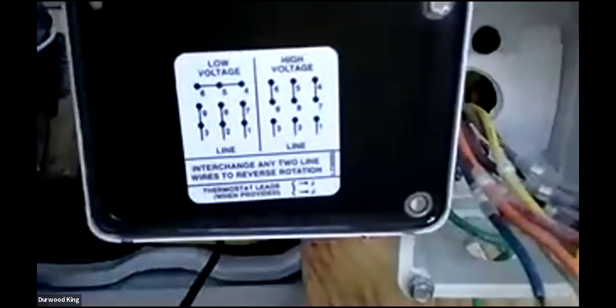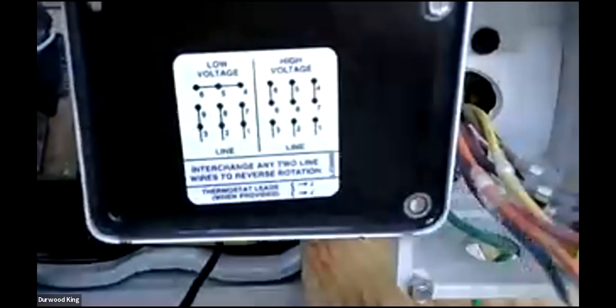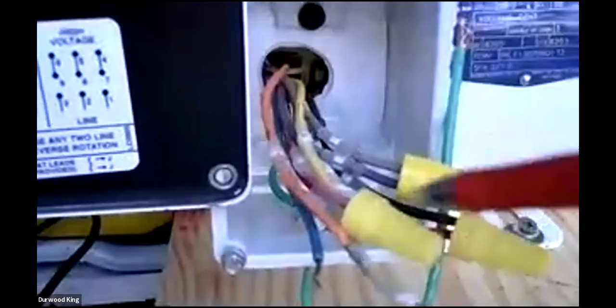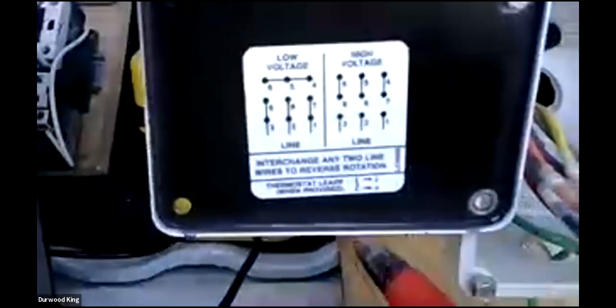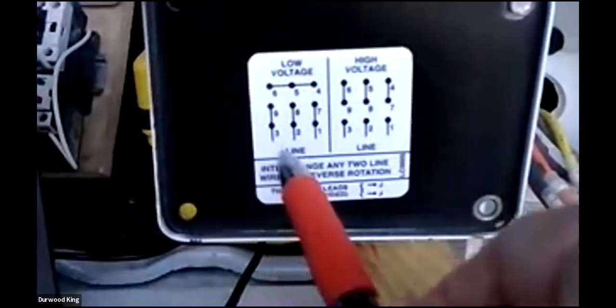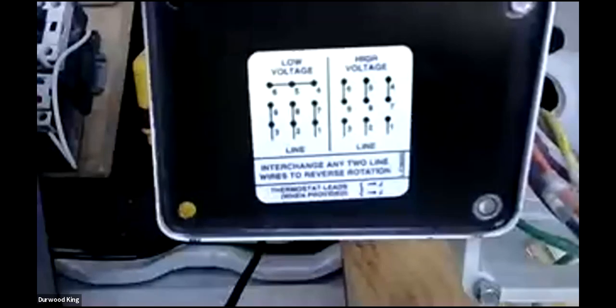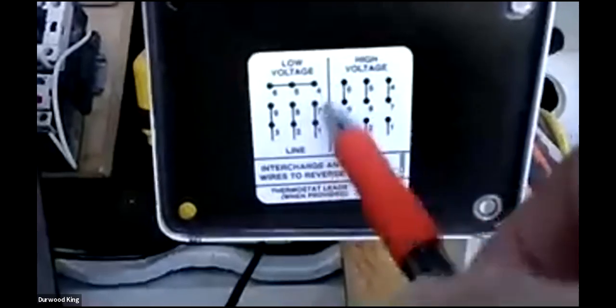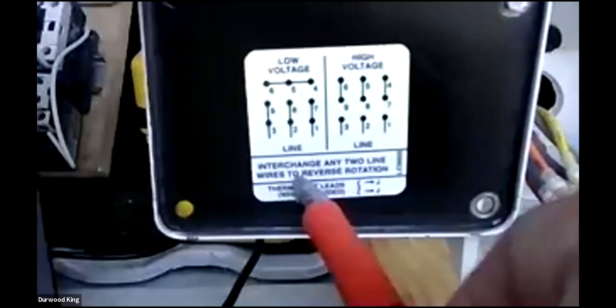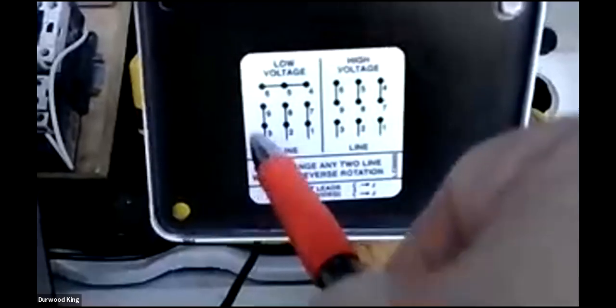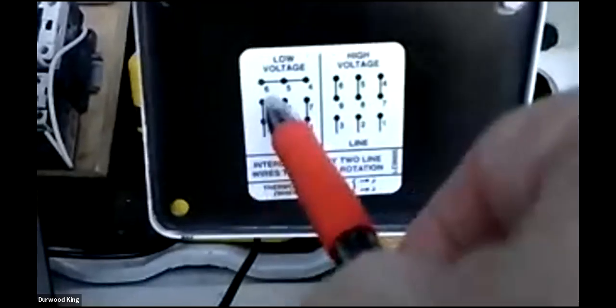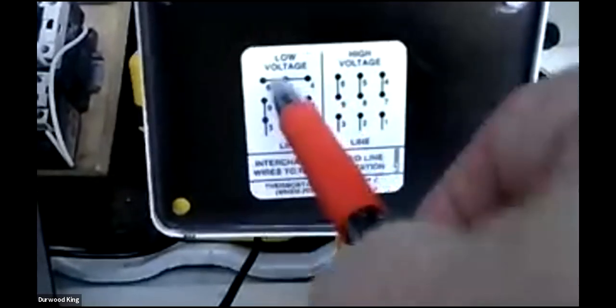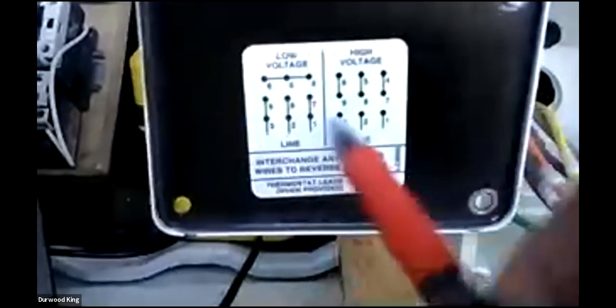Yeah. But if you wire low voltage, then everything is going to be in 3s. All the wire nuts over here, like what you wired at the school, there's going to be 3 in each one, because the incoming wire from the starter is going to join with a 1 and a 7 in the motor, and that's going to put 3 wires together in that wire nut. And your line 2 from the starter will join with 2 and 8. That gives you 3 wires. And then your third leg from the starter ties with a 3 and 9, it gives you 3 wires. So everything's in 3s. And then you get 4, 5, and 6 together. That's also 3. So everything's in 3s here, everything's in 2s here.